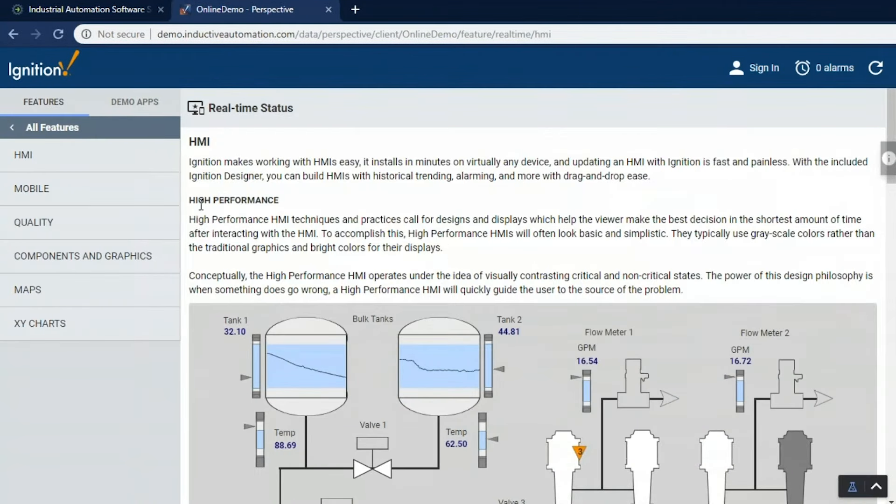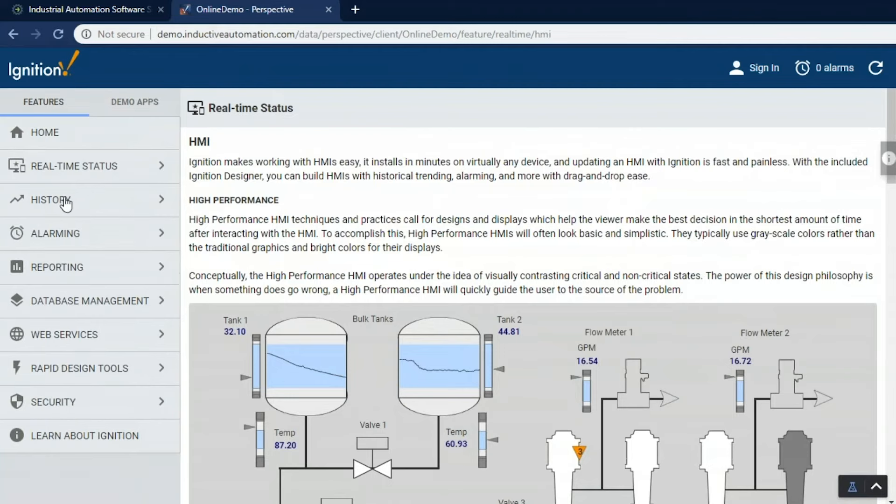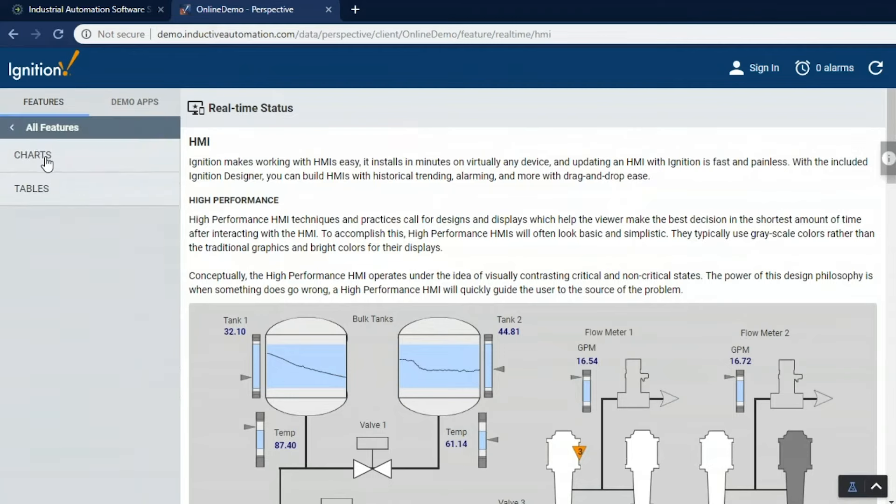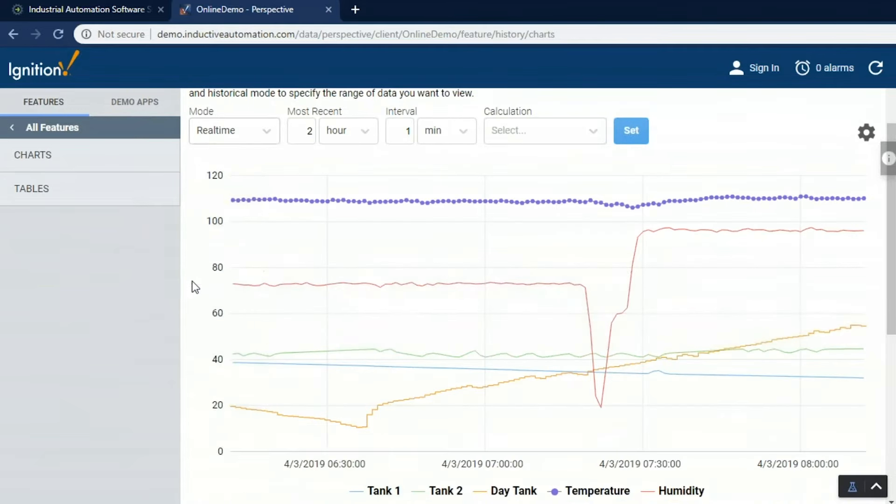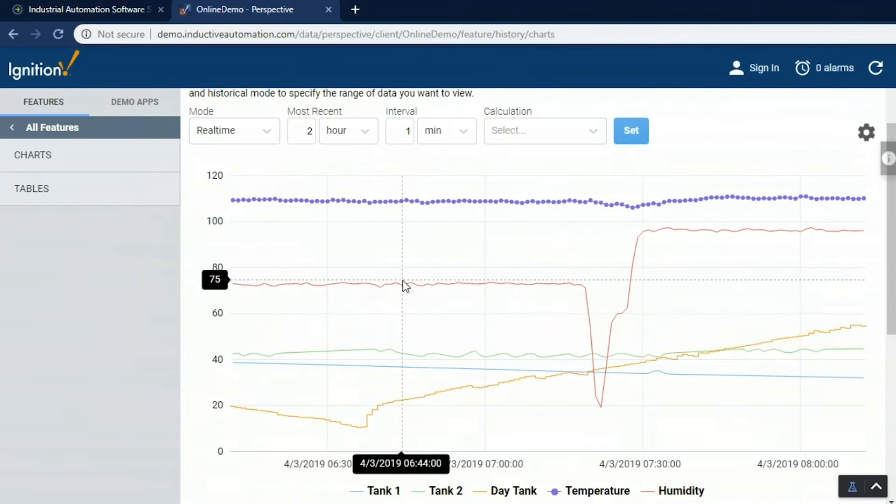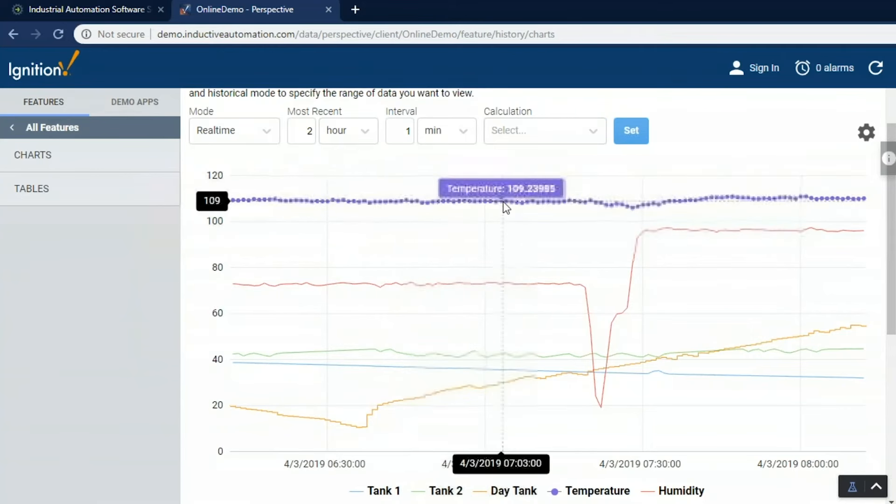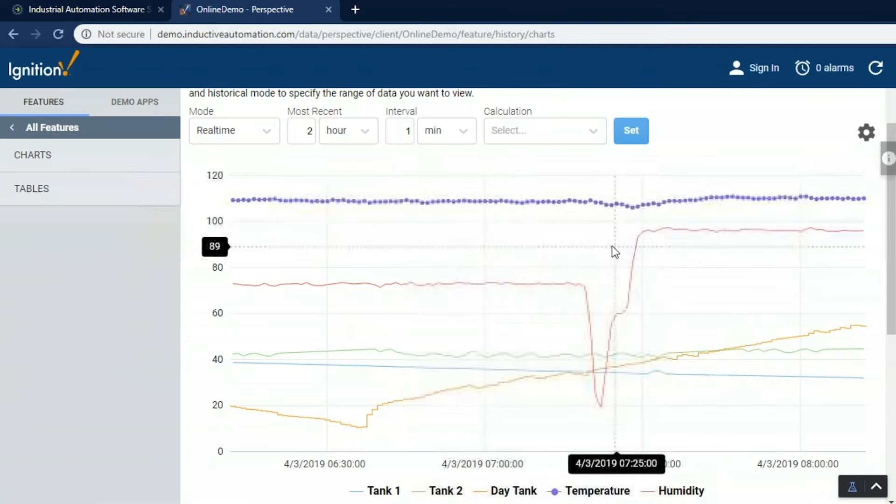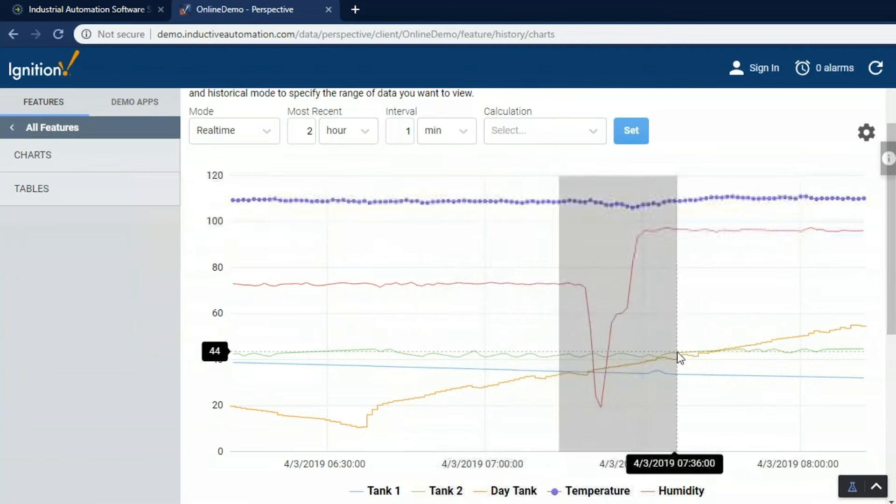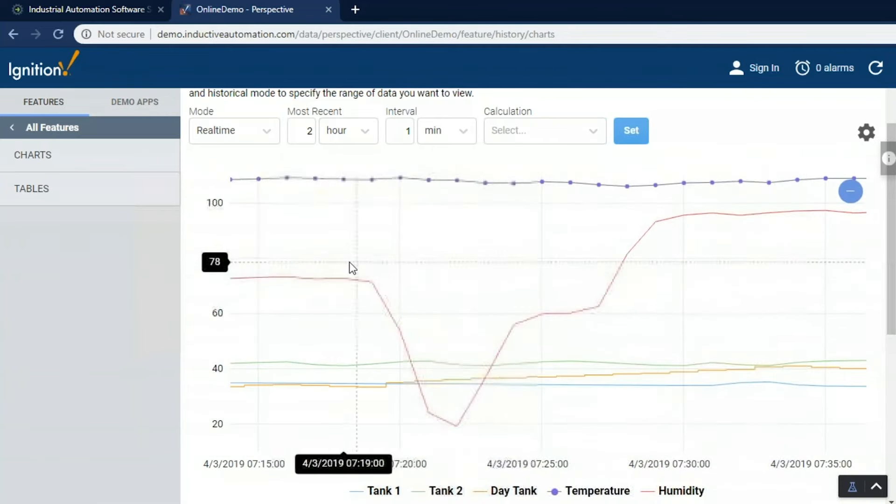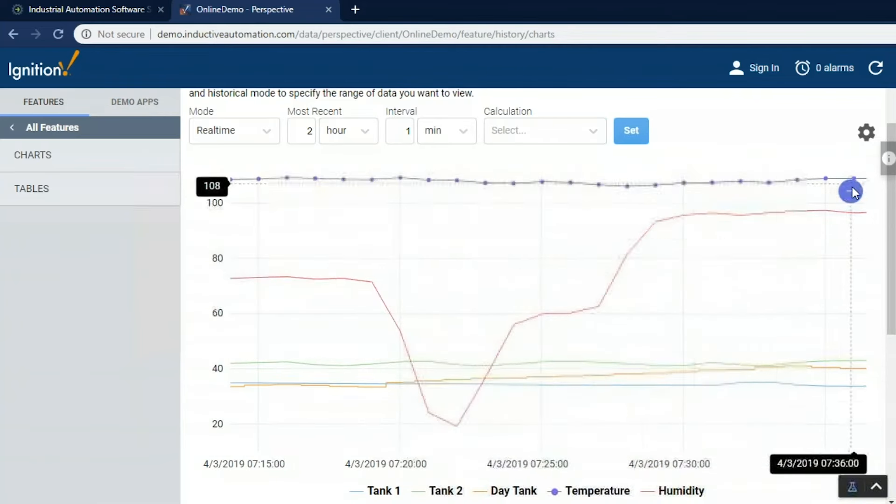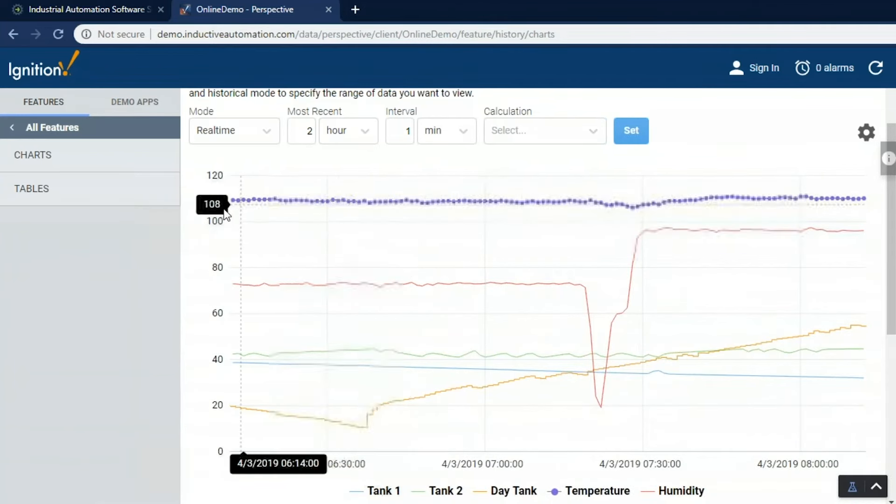Let's go and look at some other features here of the demo project. Let's look at history. We can take any tags, log them to a SQL database over time so we can see charts and calculations of that information. Here I'm looking at the last two hours broken up into one minute intervals. We can also apply calculations and change that start date end date. I can see my information, I can zoom into it, I can see the X trace of the values at given times, zoom back out.